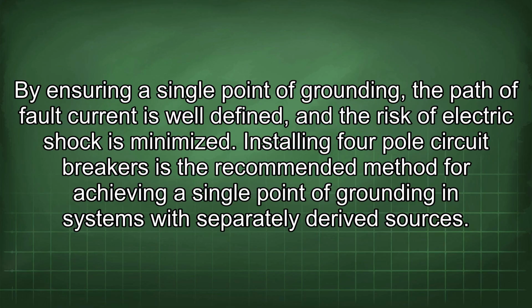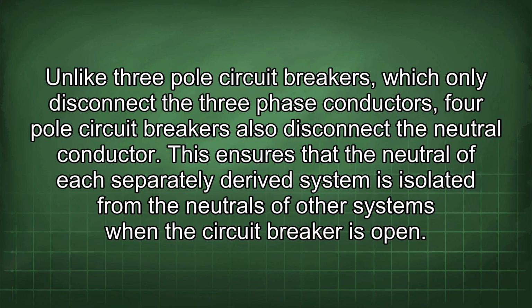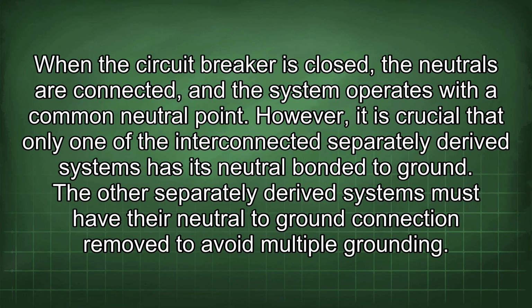Unlike 3-pole circuit breakers, which only disconnect the 3-phase conductors, 4-pole circuit breakers also disconnect the neutral conductor. This ensures that the neutral of each separately derived system is isolated from the neutrals of other systems when the circuit breaker is open. When the circuit breaker is closed, the neutrals are connected, and the system operates with a common neutral point. However, it is crucial that only one of the interconnected separately derived systems has its neutral bonded to ground. The other separately derived systems must have their neutral to ground connection removed to avoid multiple grounding.